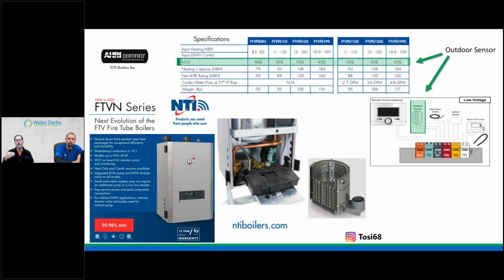Again, it's all about return water temperature, lowering the water temperature. This piece of equipment has now become everyday, yet I never see outdoor sensors, nor do I see a wet condensate trap or a neutralizer. It's nice that we have these things, and I think what drove this was the lack of space. We didn't really care about efficiency still. We didn't really care that they're paying for all that engineering to achieve this high efficiency. It's just engineered to do that. You need to make it do that when you apply it into your systems, and that, again, is lowering water temperatures.